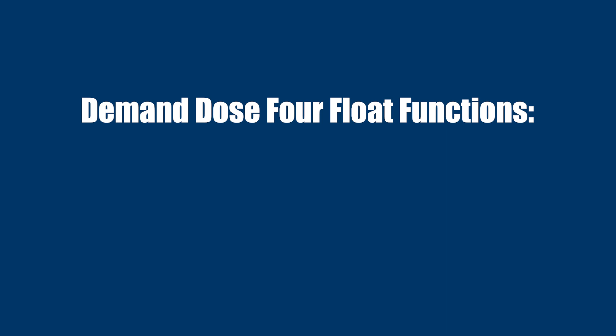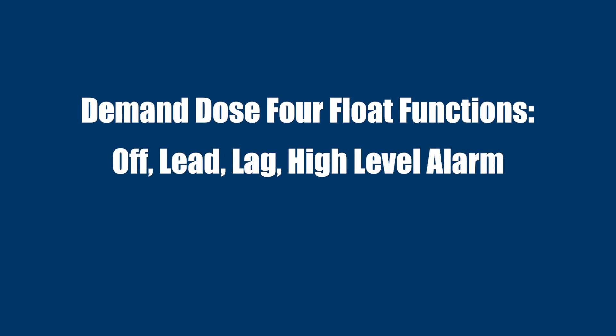Demand Dose Setup. Now we can set up the panel for our first system. A demand dose system with four floats where the float functions are off, lead, lag, and high-level alarm.